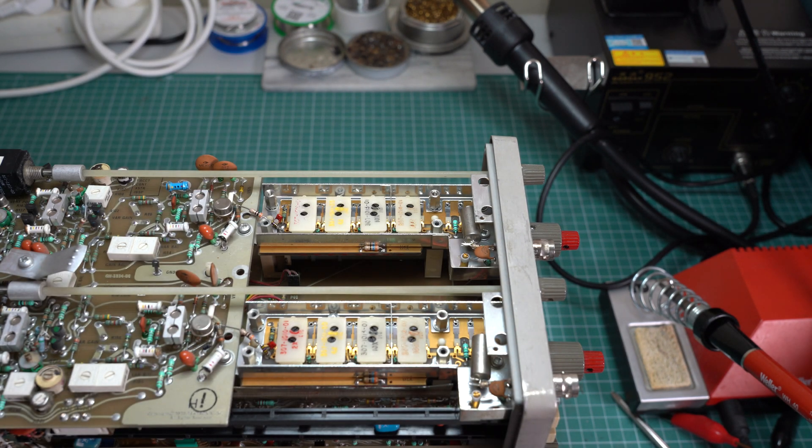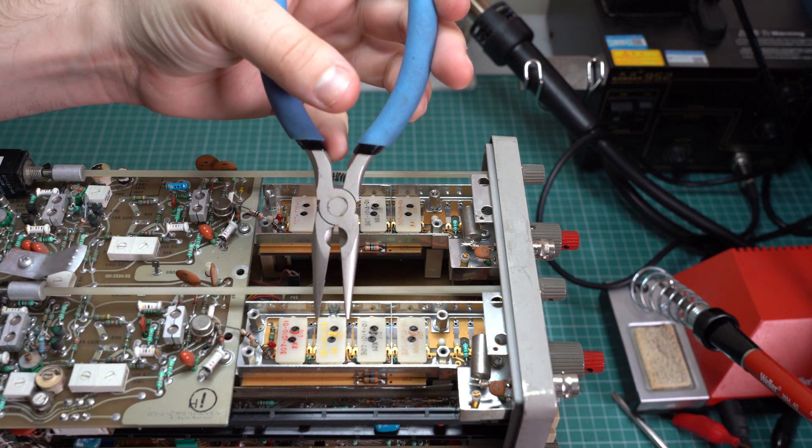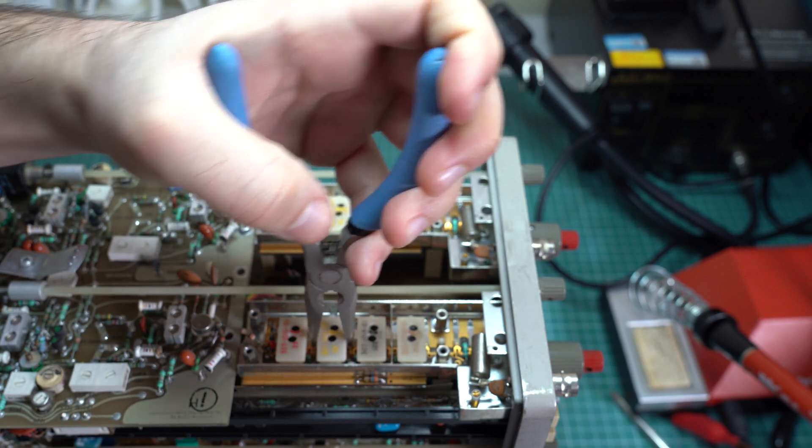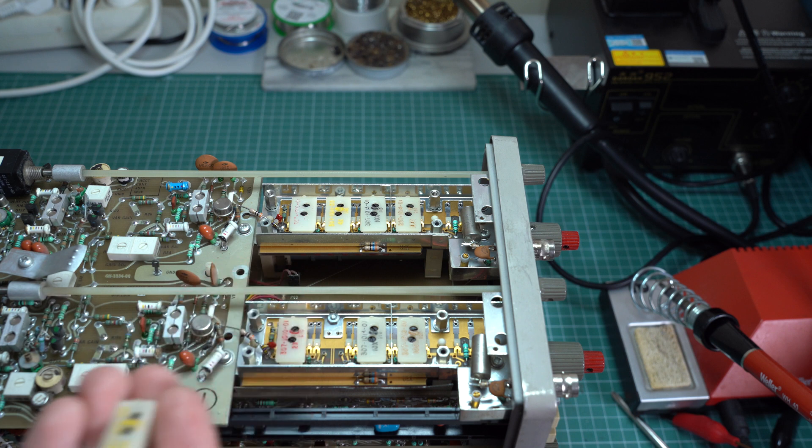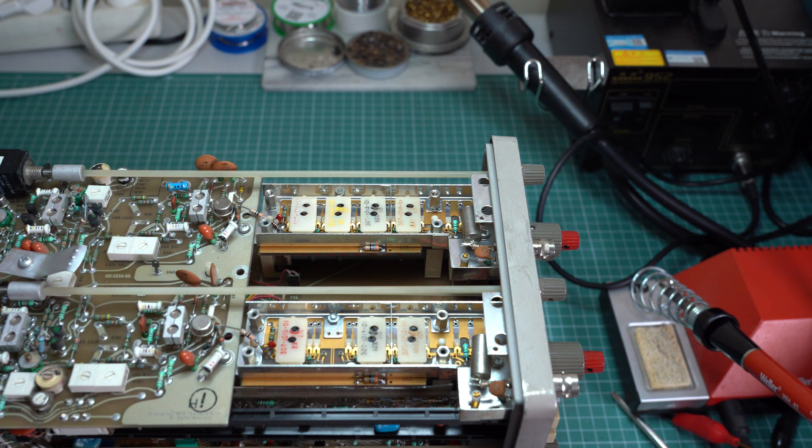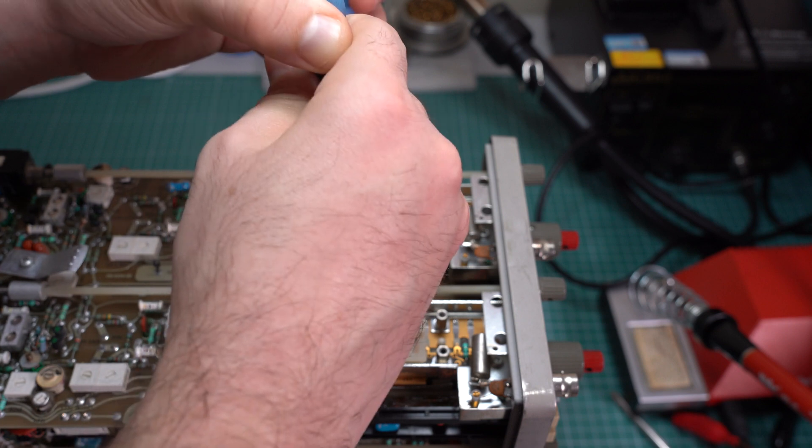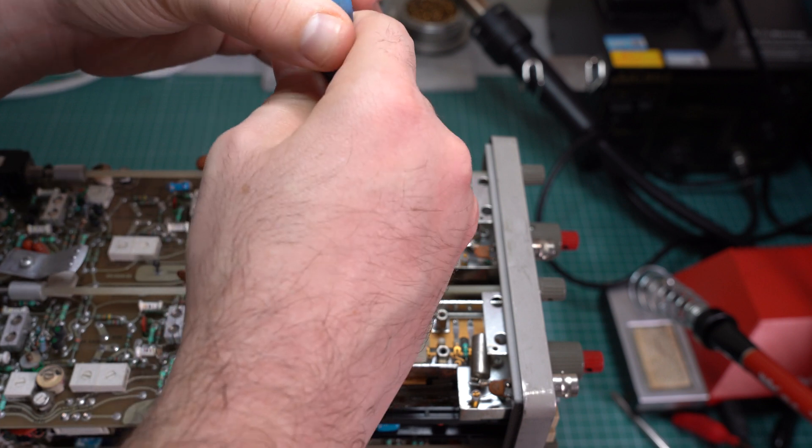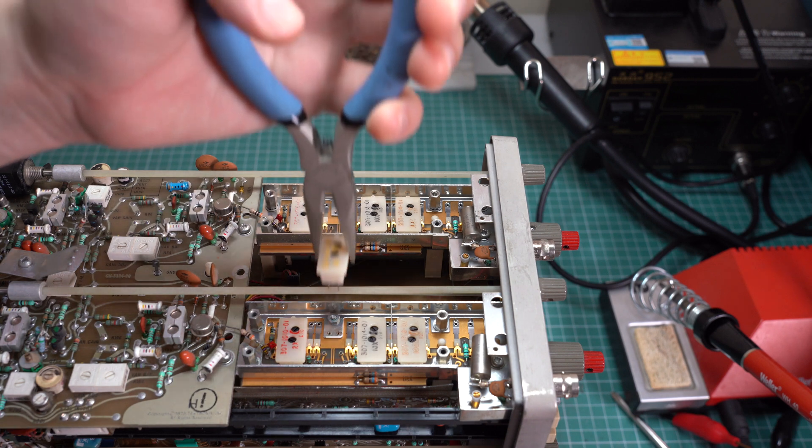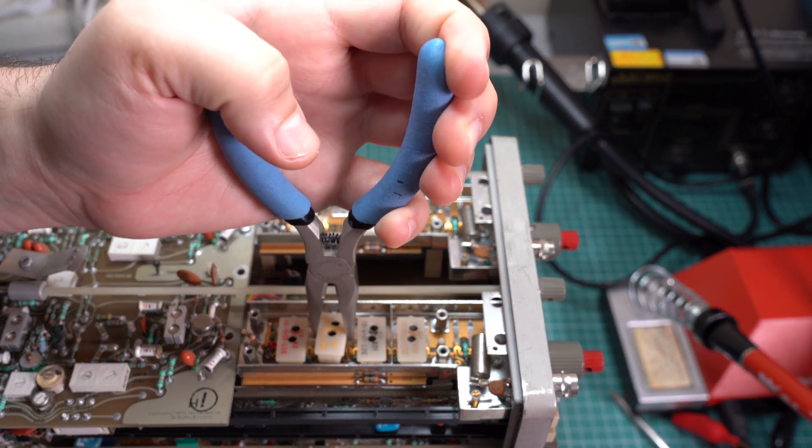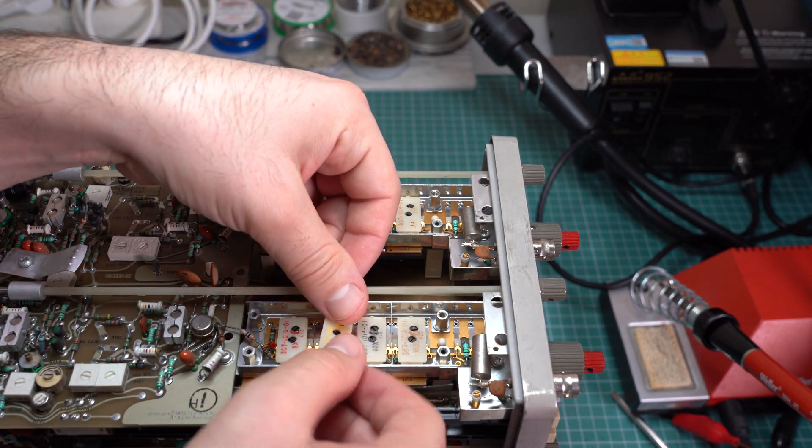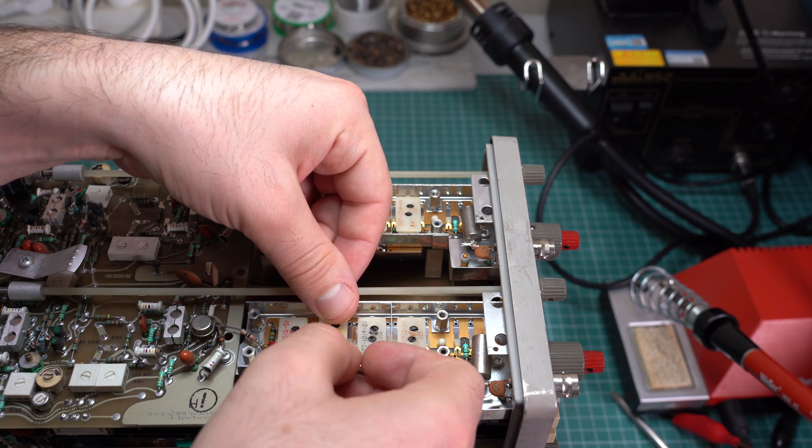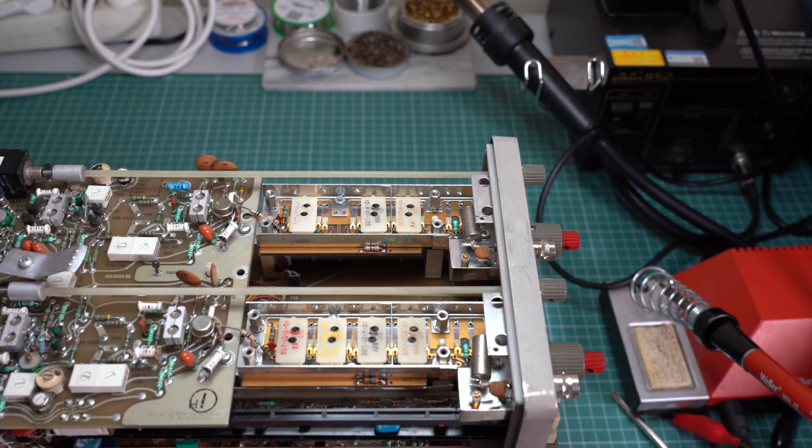Okay, we are in. And now let's carefully remove the attenuator. This one is out. This is okay. So let's try to put the broken one in here. These are very delicate so I'm very reluctant to do this but I think this will help us isolate the fault.